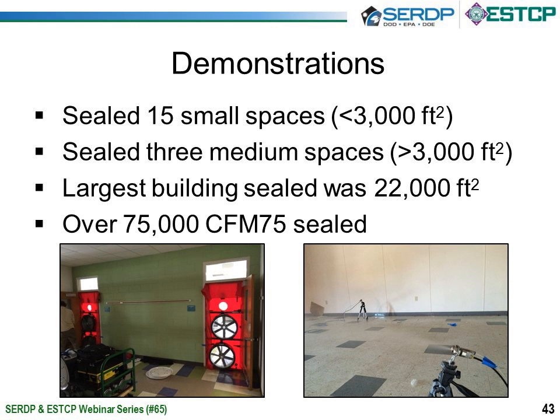Overall, we sealed 15 smaller spaces. These are spaces under 3,000 square feet. And this could have been a space within a building that was cordoned off, so you could compartmentalize a space within the building or a standalone building. We also sealed 3 medium-sized buildings, so that was anything larger than 3,000 square feet. And the largest building that we sealed was 22,000 square feet for this project. Overall, we were able to seal 75,000 CFM at 75 pascals throughout the whole project.